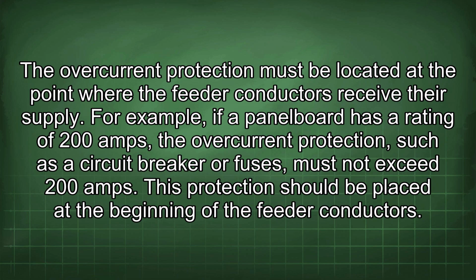The overcurrent protection must be located at the point where the feeder conductors receive their supply. For example, if a panel board has a rating of 200 amps, the overcurrent protection, such as a circuit breaker or fuses, must not exceed 200 amps. This protection should be placed at the beginning of the feeder conductors.